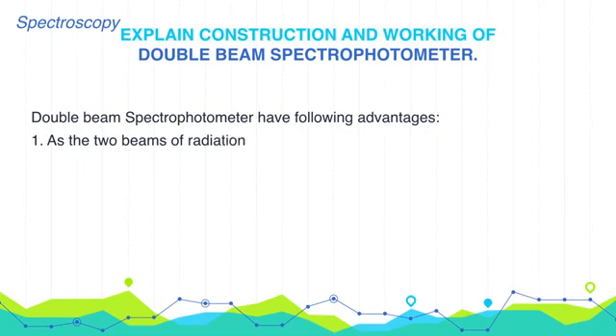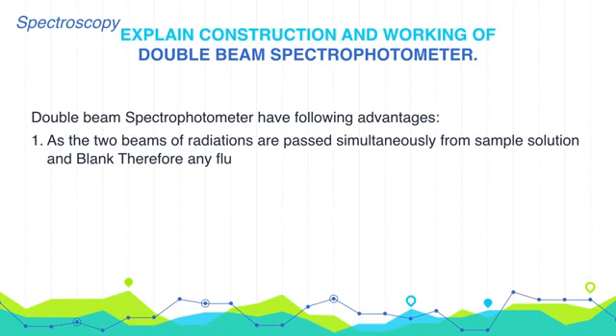Double beam spectrophotometer has following advantages over single beam spectrophotometers. As the two beams of radiations are passed simultaneously from the sample solution and blank, therefore any fluctuation in voltage can be compensated or cancelled.